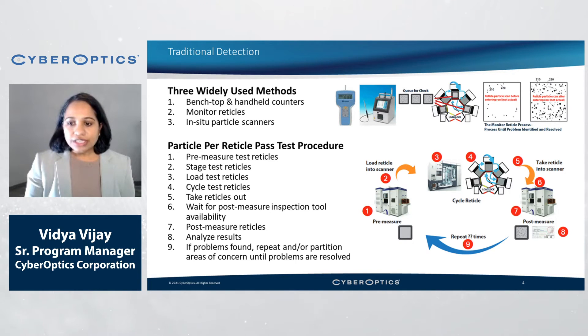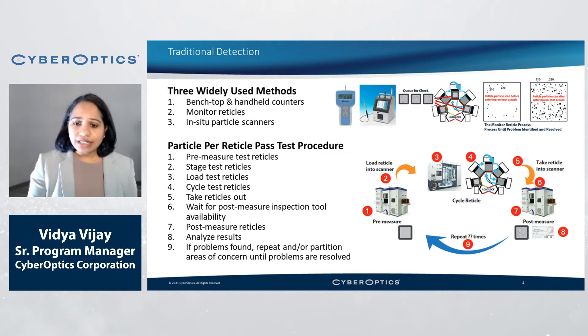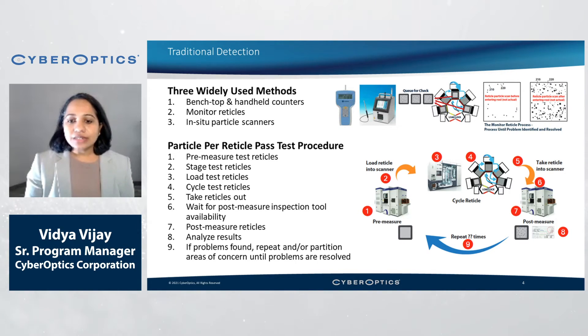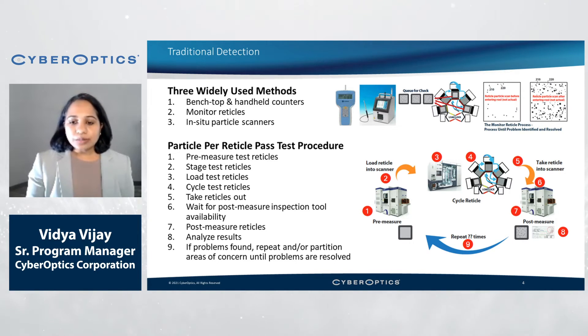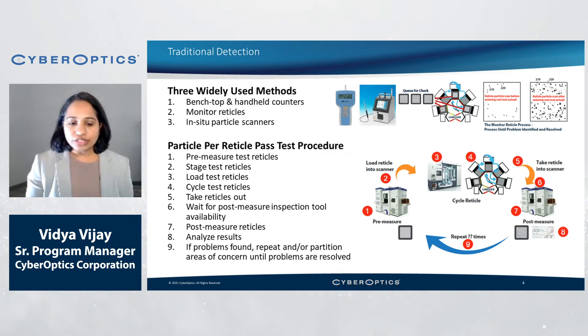Photolithography tools scanned with monitor reticles and in-situ methods routinely have excessive particles. The in-situ scanner will scan monitor reticles going in clean, but intermittently exit with a substantial amount of particles of unknown origin. In summary, traditional methods for particle detection are not ideal for identifying the particle source, making particle contamination a constant source of frustration for scanner operations.